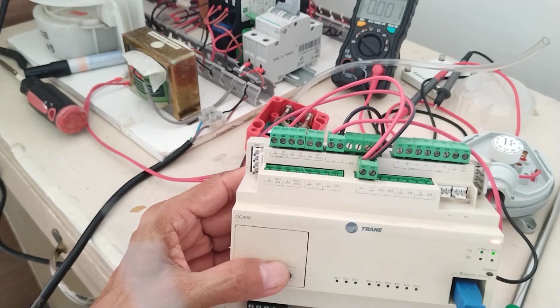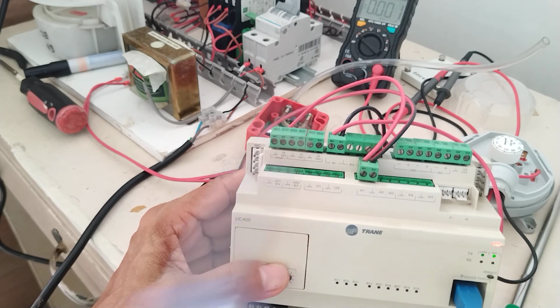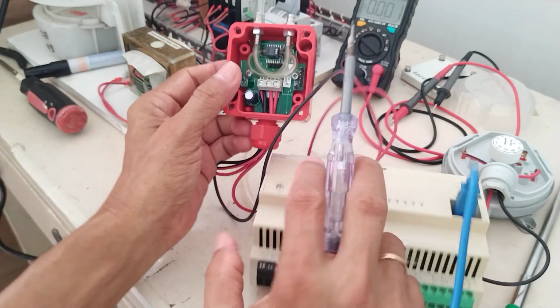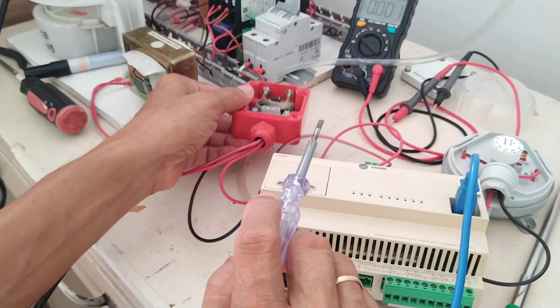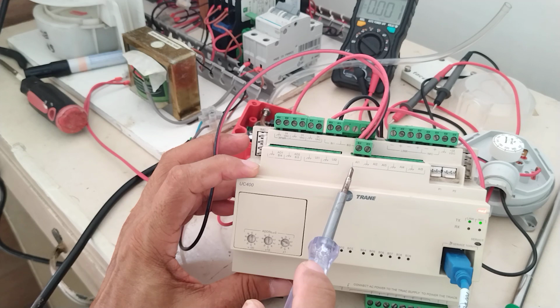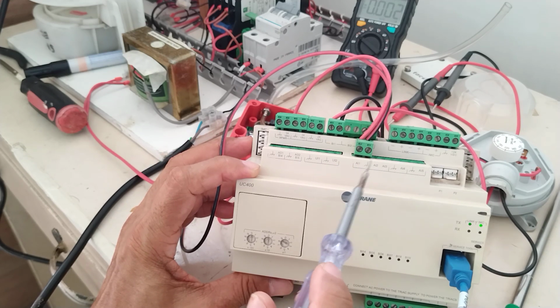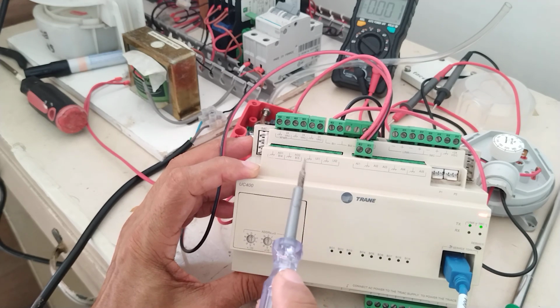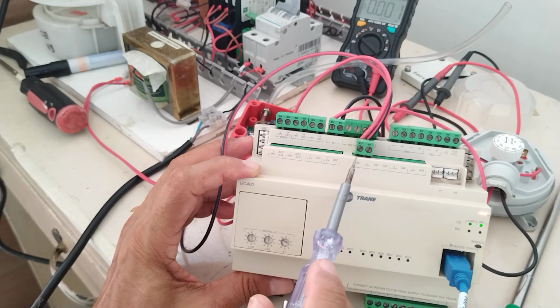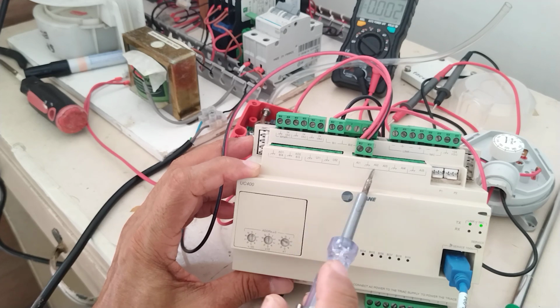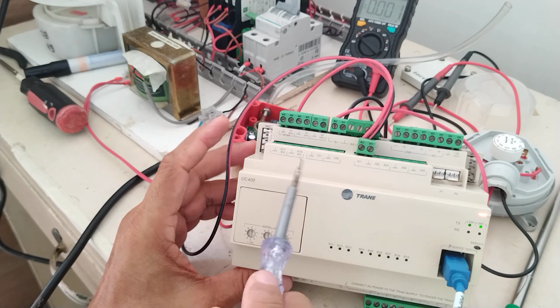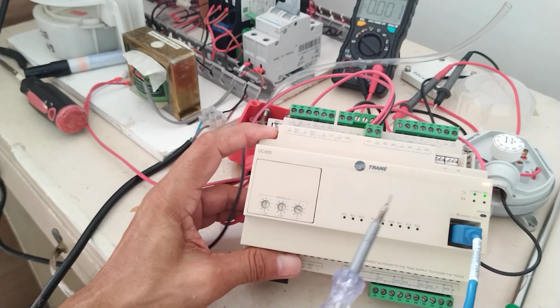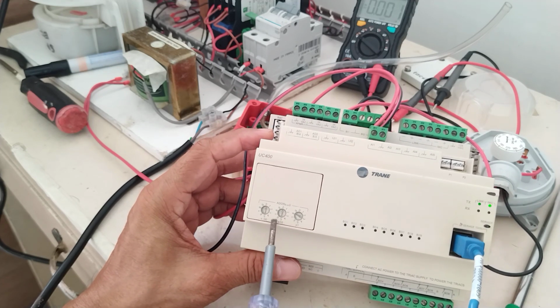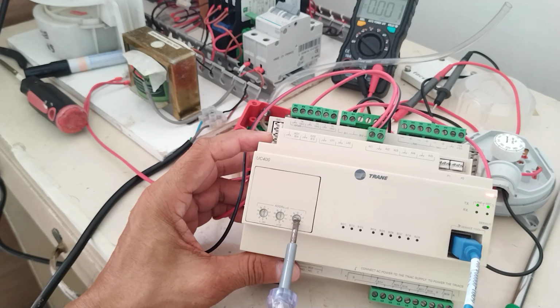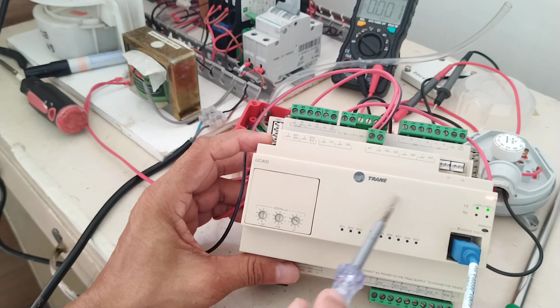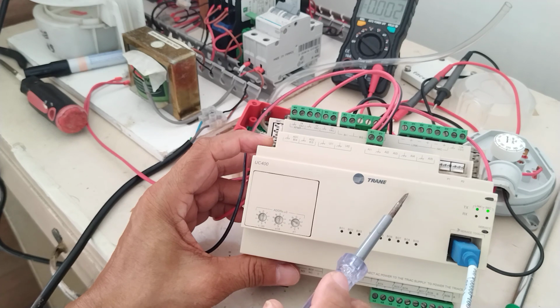Then, you have to do some engineering or scaling. Let's say 0 to 10 volts. Okay? Now, how are you going to do the scaling, the engineering? Now, as you can see here, the maximum range is 50 millibar. So, meaning, if you will receive 0 volts here, meaning 0 millibar, okay? Then, if you will receive 10 volts DC here, meaning it's in the maximum range, 50 millibar. So, you have to configure that one in your computer or in your BMS workstation, okay? So, you need also to do proper configuration of the channels, okay? So, again, this is a BACnet controller, okay? Now, of course, if you are the BMS engineer, you have to address properly your BACnet controller because you need to input also this one if you want to monitor the control and monitoring points associated in this UC400.